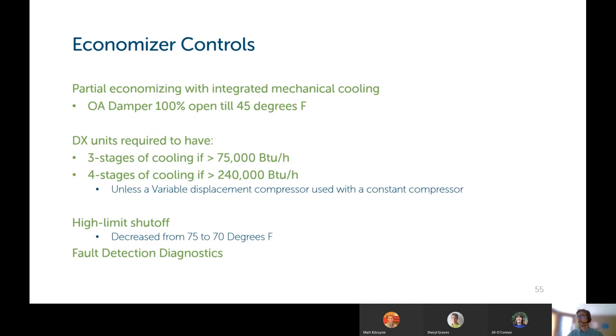Economizer controls. You need to be able to do partial economizing with integrated mechanical cooling so that you can have the outdoor air damper open 100% down to 45 degrees Fahrenheit. Direct expansion units are required to have at least three stages of cooling if they're greater than 75,000 BTU per hour, and at least four stages of cooling if they're greater than 240,000 BTU per hour. If you have one constant capacity compressor and a variable displacement compressor, you can use that in lieu of the different stages of cooling, where the variable compressor will modulate the capacity.